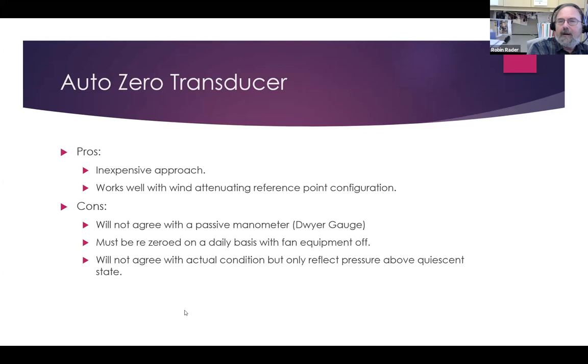Another thing about the auto zero transducer is it wouldn't work for systems that have to run 24 hours a day. So for instance, in hospitals, you've got no point where you can zero your transducer because you've got the difference between reliever and exhaust air versus the amount of incoming air, and you wouldn't know what that difference was. Also, I already spoke to that, so keep going here.